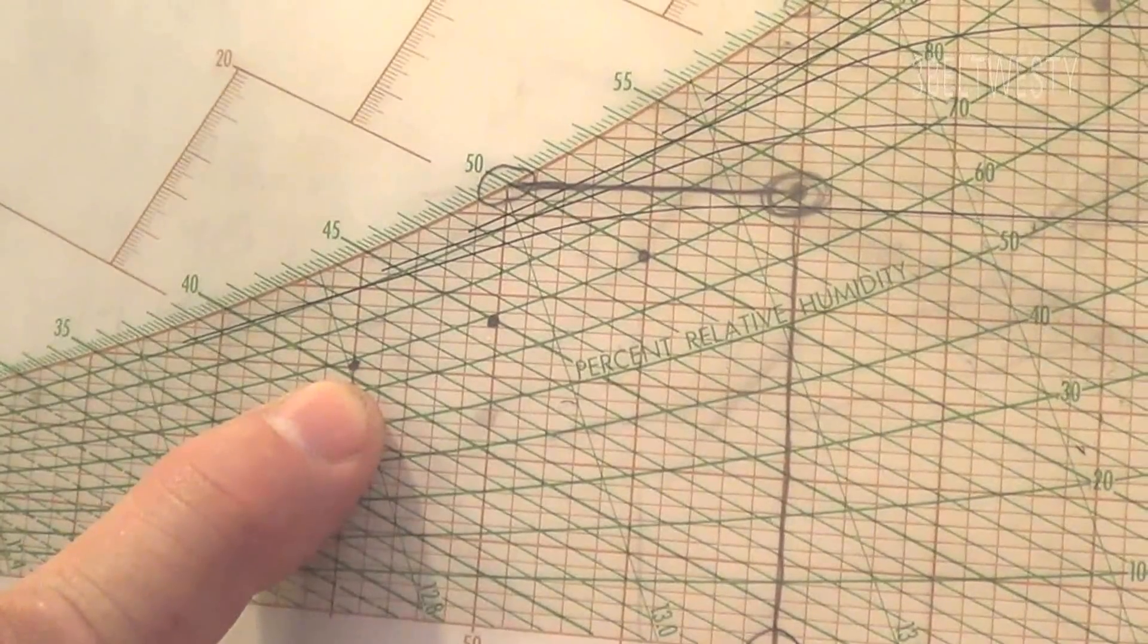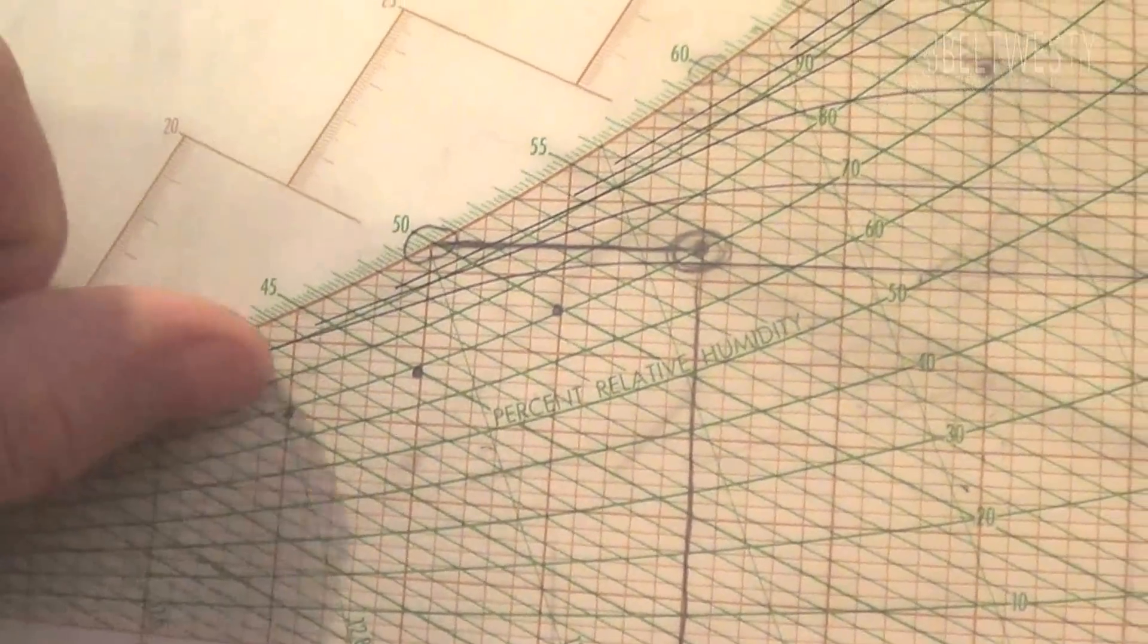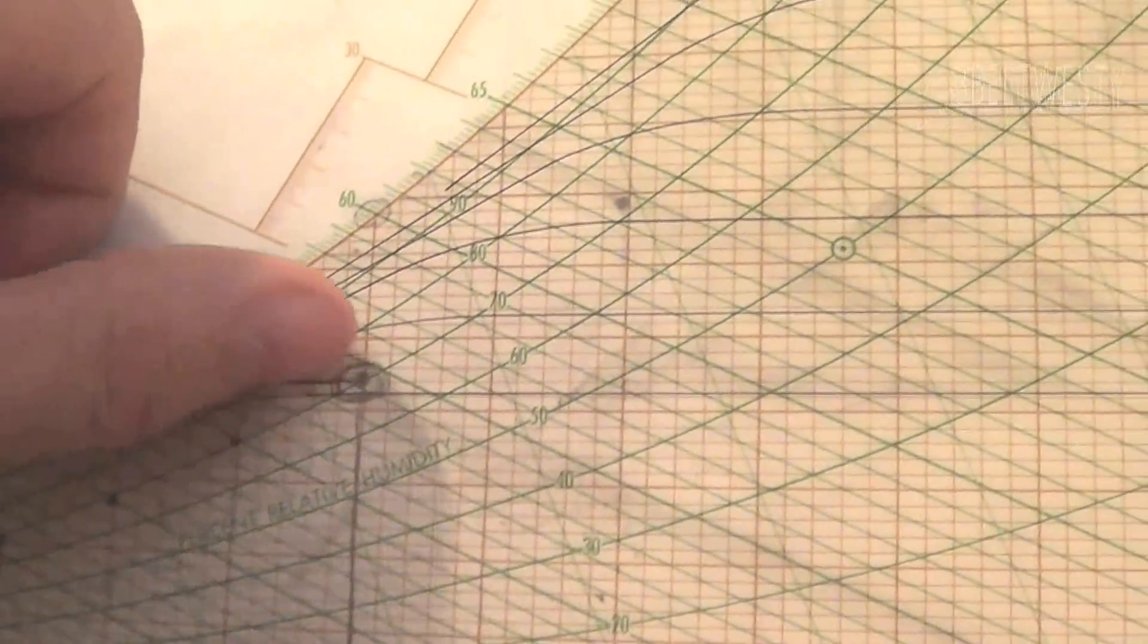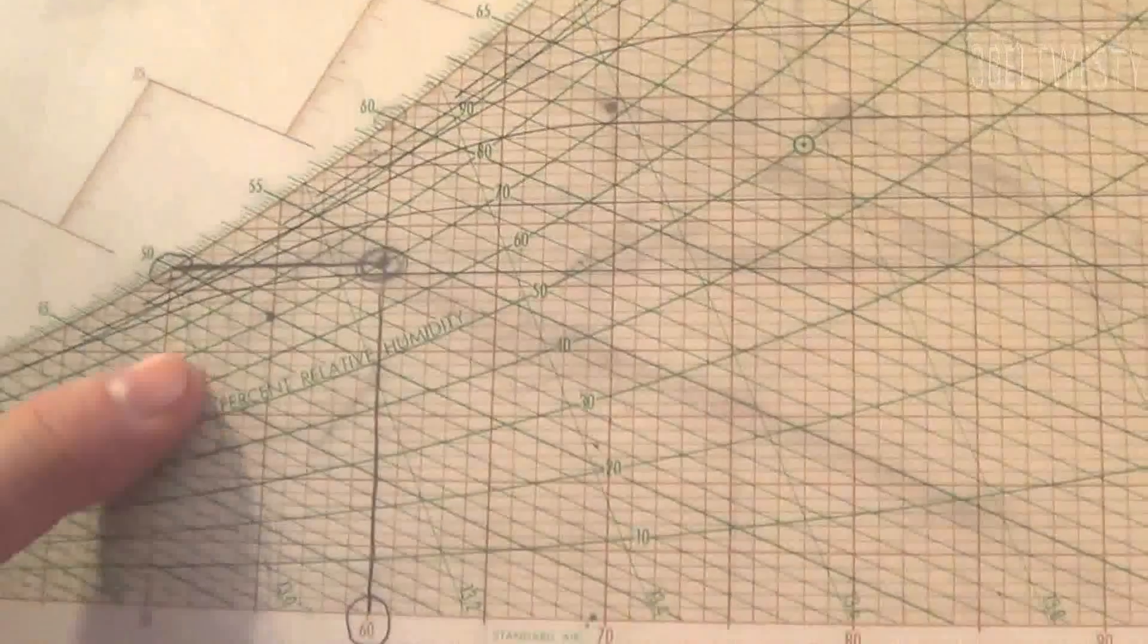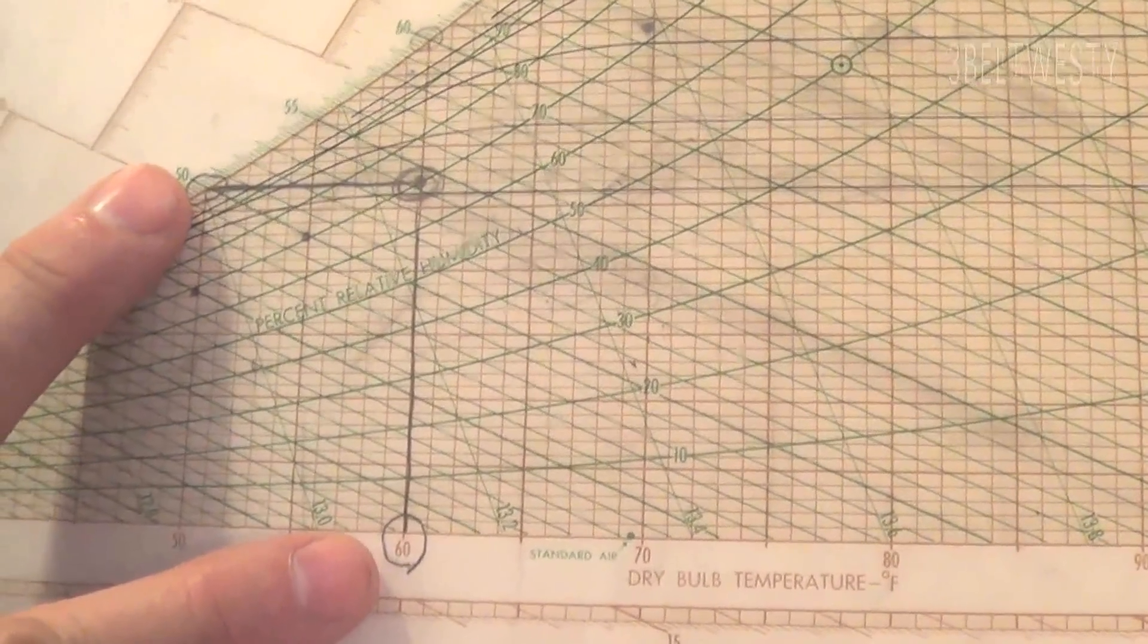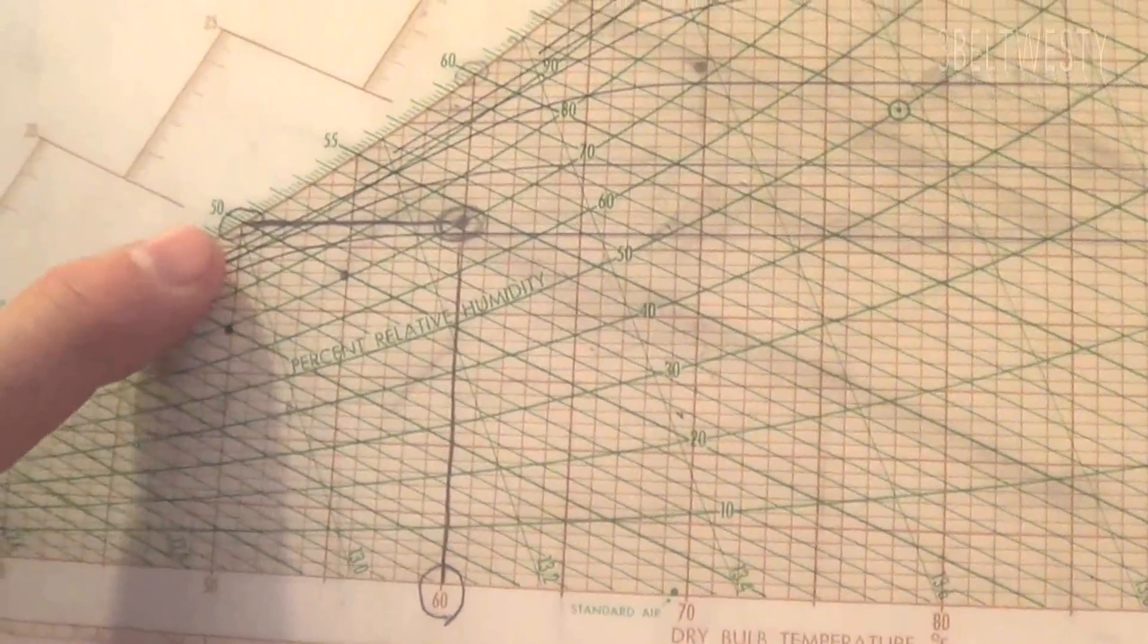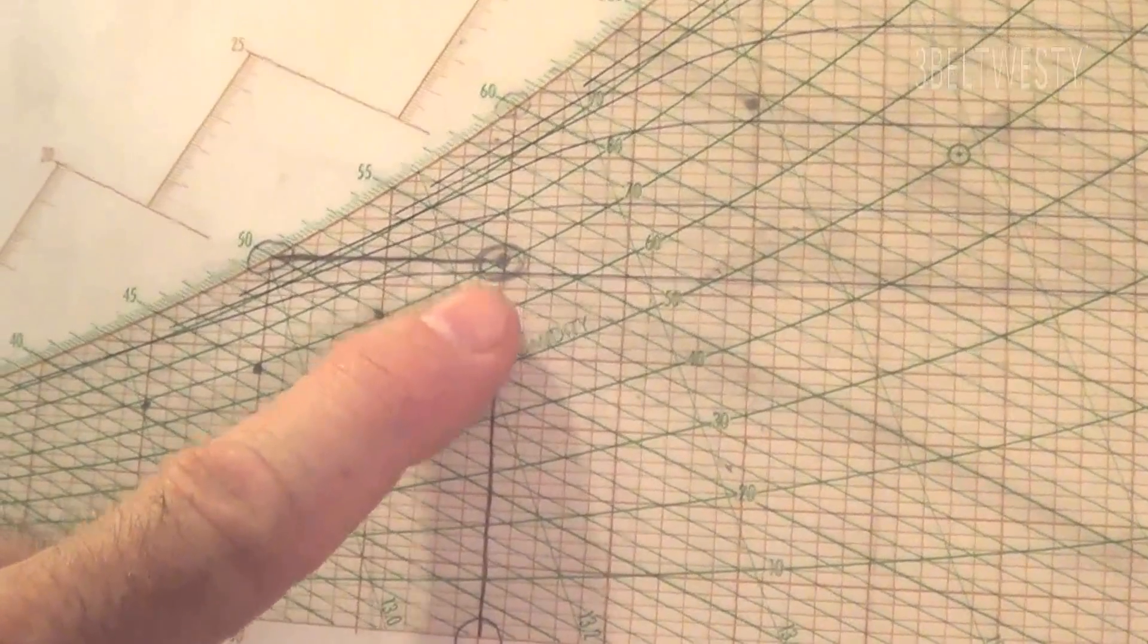So this line here of 70% relative humidity is roughly a good swag—it's a 10 degree differential between the dry bulb and the dew point.